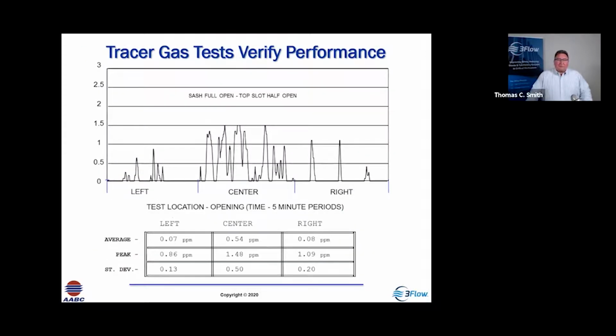Now, oftentimes what we see when we're looking at tracer gas data in the breathing zone, this is on the left, we see some spikes. In the center, we may see some of the highest escape from the hood. And we look at this average over this period of time in order to get our average concentration. We also look at peak concentrations. So in this particular case, this hood would fail because it wasn't meeting the Z9.5 criteria of 0.1 parts per million for the ASHRAE 110 test. So you can't really say that it failed the ASHRAE 110 test. That's just a method of testing. What you can do is say it failed to meet the Z9.5 criteria for that test, or it failed to meet the owner's criteria, but ASHRAE 110 does not have a pass-fail.